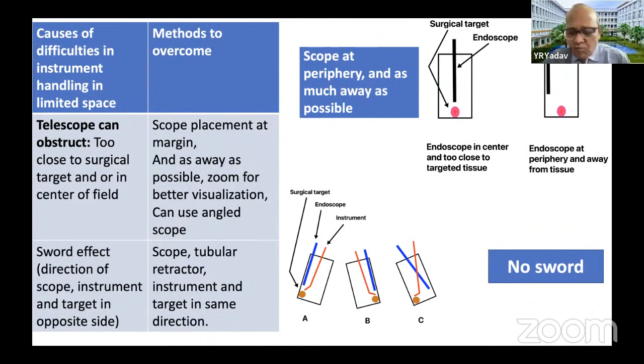So another cause of difficulty in handling of instrument in the limited space, the keyhole surgery, is when you use thick instrument and straight instrument. This is the example. See, there is an endoscope and these are two instruments, and there is a keyhole surgery, limited space. So if you use thick instrument, then the whole space will be occupied by the telescope and the instrument, and you will not be able to do bimanual dissection. No movement is possible, so surgery will be difficult. Whereas if you pass the slender instrument and single limb instrument, then there is sufficient space for the two instruments to manipulate. There may be difficulty in reaching the target at the corner of the target.